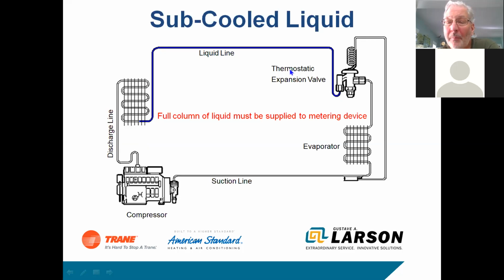If you don't have any subcool, if it's low, if you've got 2 or 3 degrees of subcool, then you're not feeding liquid to the valve. And if you're not feeding liquid to the valve, it doesn't know how to feed the system. So you're going to have high superheat. You're going to have high temperature gas here. It's not going to cool properly. The system's just not going to work. This needs to see 8 to 12 degrees of superheat, and in order to do that, it has to see liquid at the valve right here.